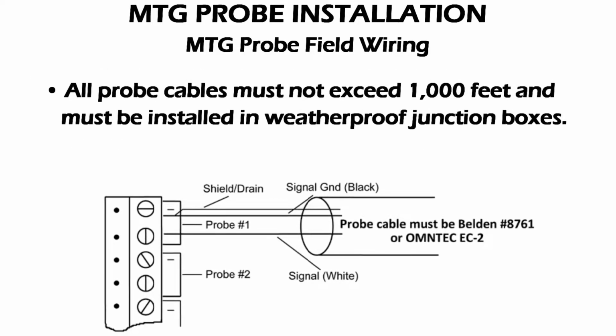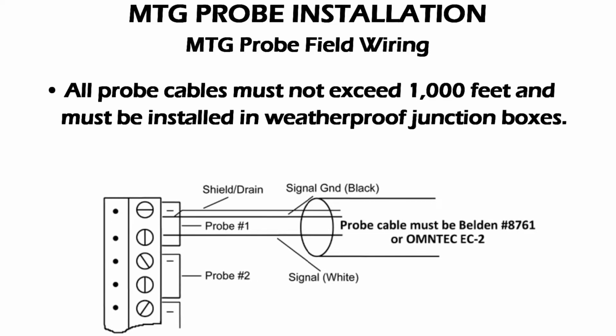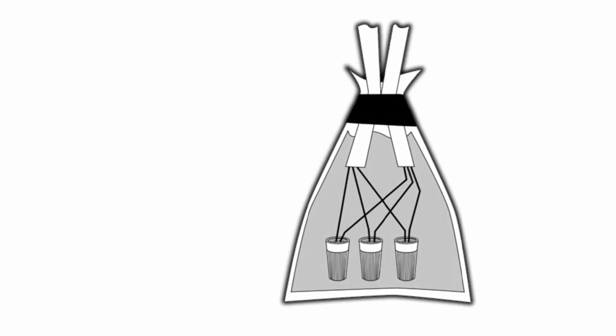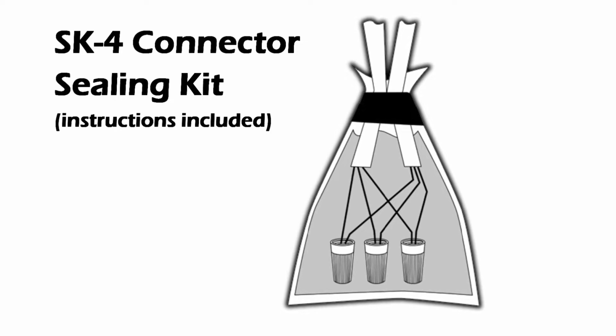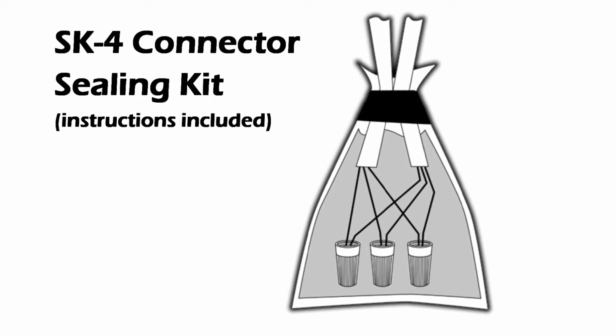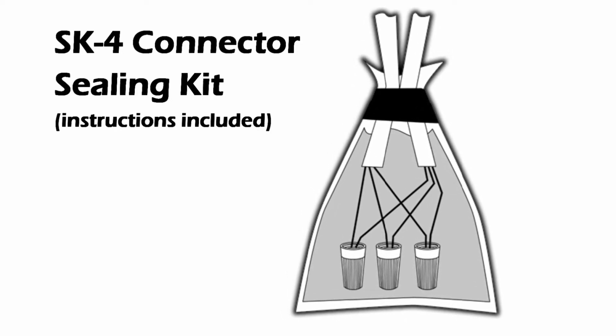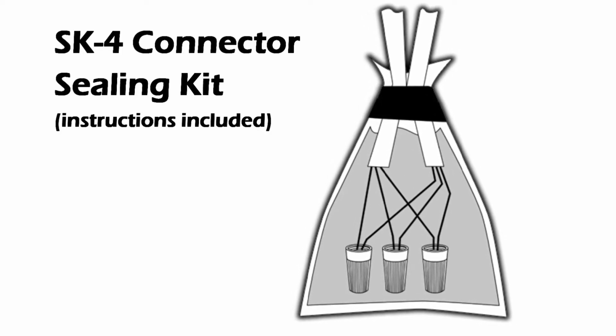All probe cables must not exceed 1,000 feet in length and must be installed in weatherproof junction boxes. Make wiring connections. Use the SK4 connector sealing kit for all splices. Instructions are provided with the kit. This completes the probe installation section.